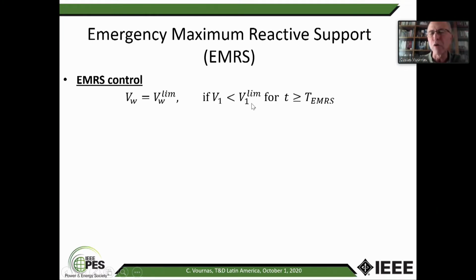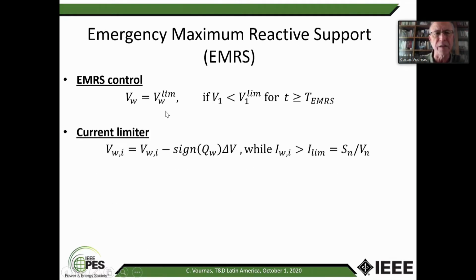And if the voltage drops below, let's say 90%, then what happens is that the set point from 1 per unit goes to the maximum permissible value. Usually this is 5% or 8% or 10%. In this simulation I'm using 10%, but this depends on the code on the distribution side, which is the maximum permissible voltage in the distribution feeder. So it switches directly to the maximum voltage and thus provides the maximum reactive support. So the maximum in the title of the method refers to the fact that you go to the limit.